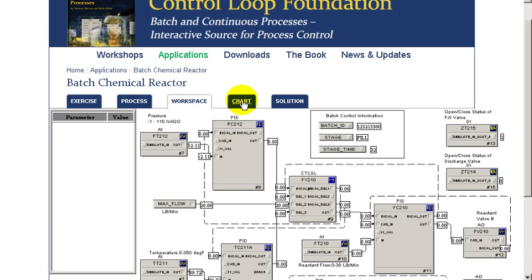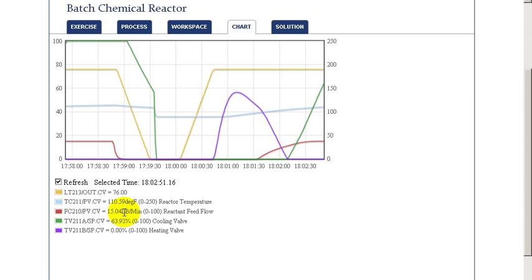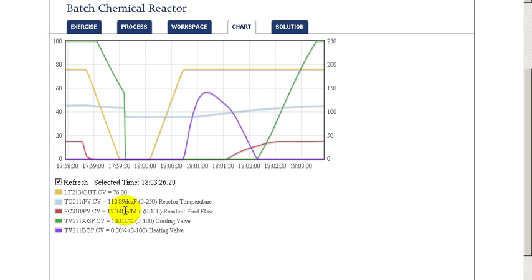Now, with a value of 20, we see that during the initial phase of the cycle, the cooling valve really has to open much quicker than before because of the exothermic reaction.